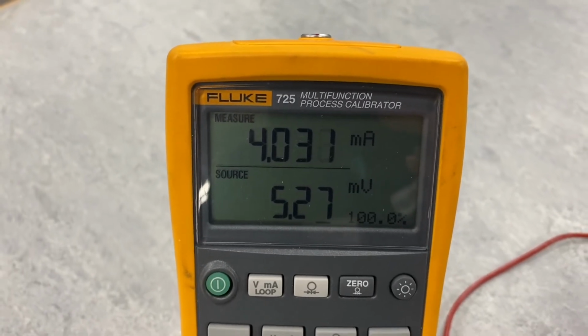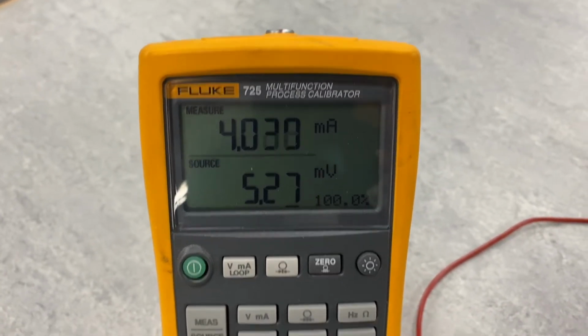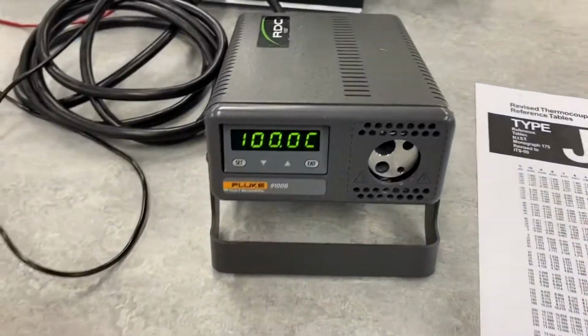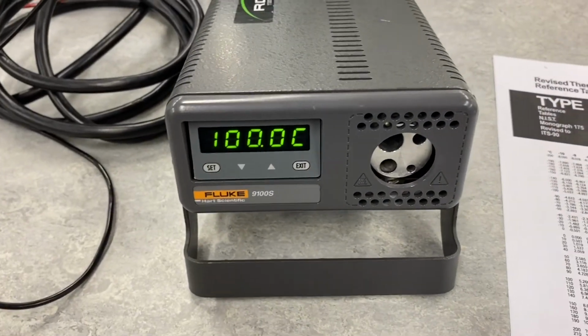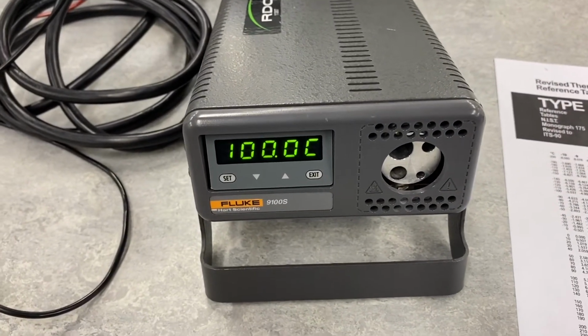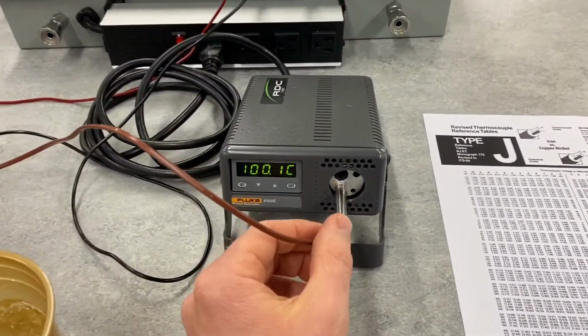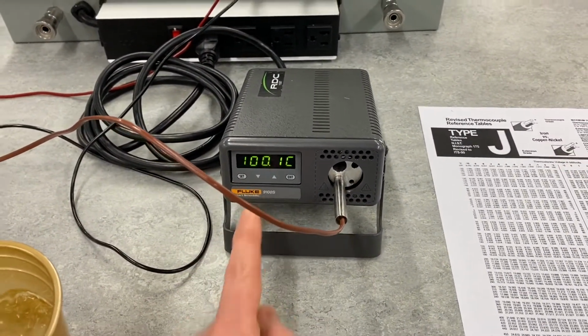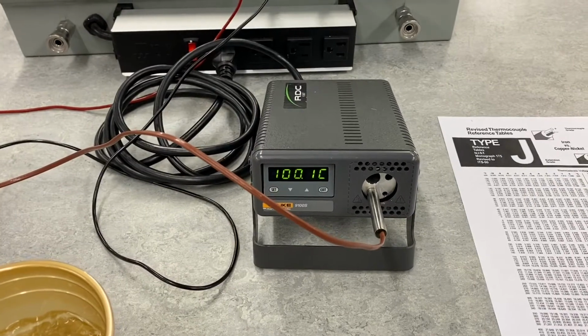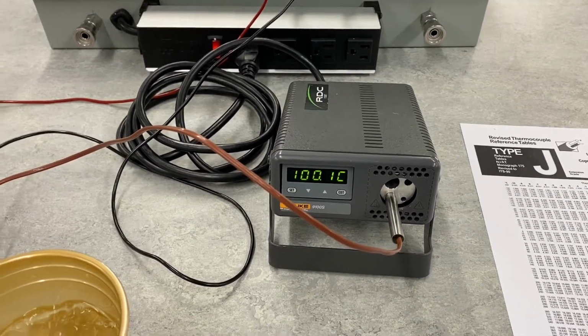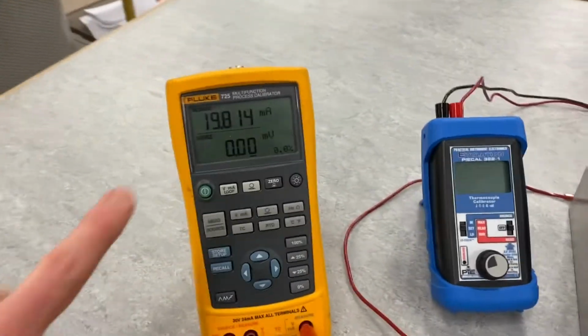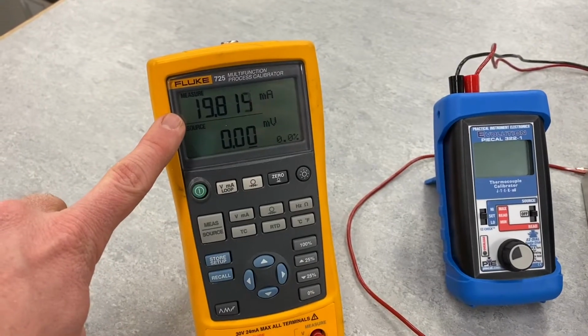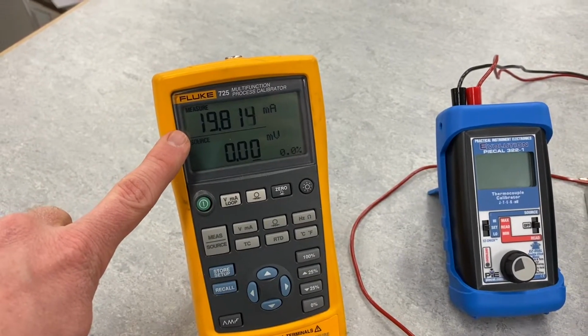We calibrated at 4. The next step here is we're going to insert the thermocouple into our dry block here just to verify our calibration. All right, so now we place the thermocouple in the dry block here. It's at 100.1 degrees C. And over here, you can see our transmitter is pretty close to 20 milliamps. It's at 19.814.